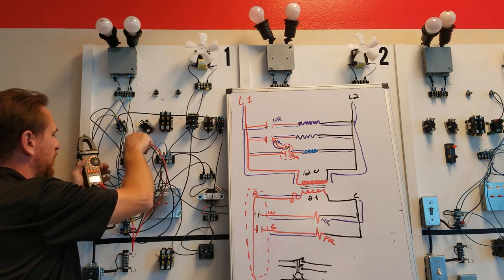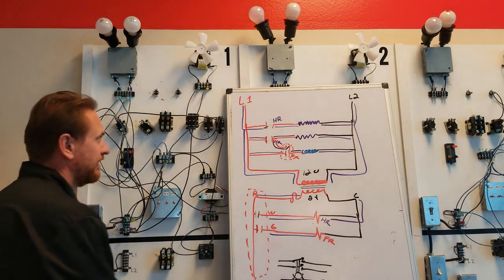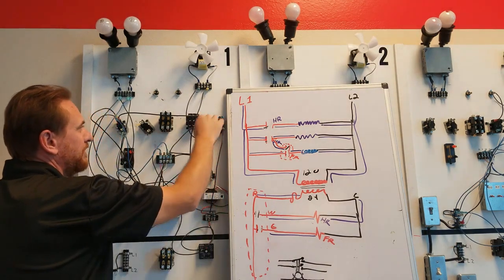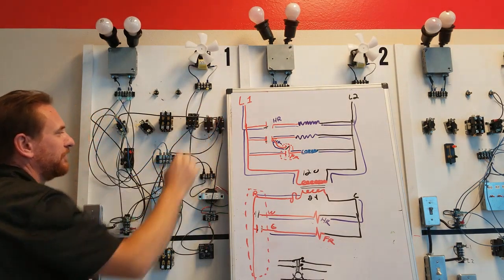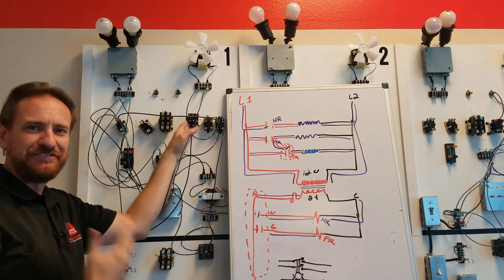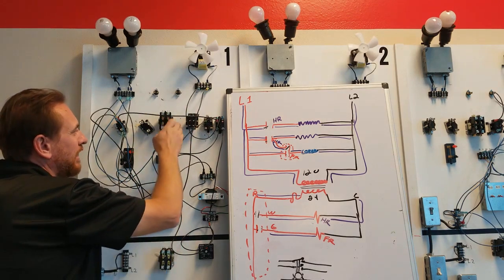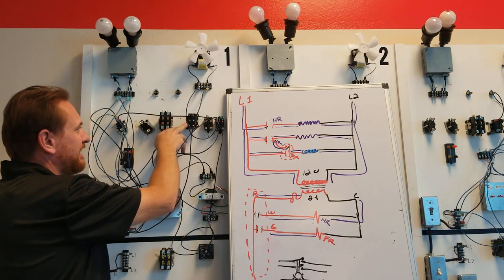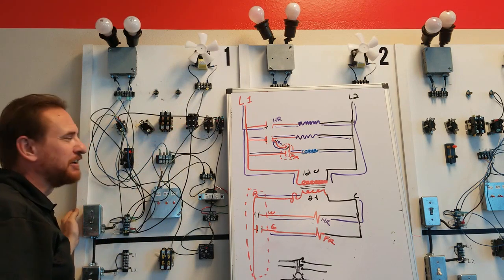With the switch open, OL, infinite resistance. So I know that this is going to be my load. This is normally open. This is normally closed. Here's another relay. Does the very same thing. What's cool about this relay, it's called a 90-340 fan relay. It's one of the most popular fan relays out there.